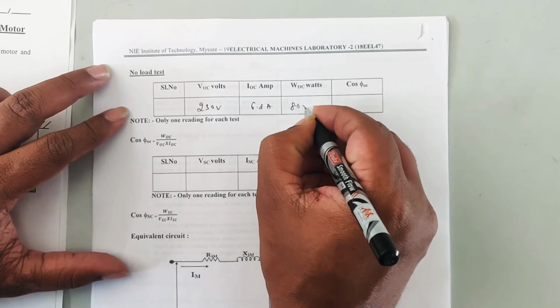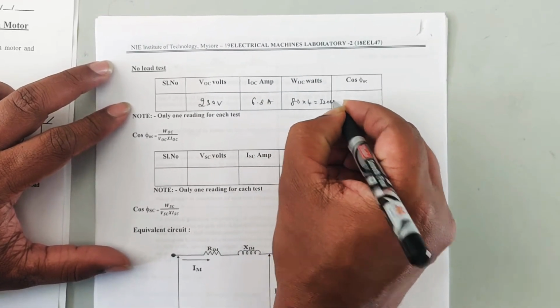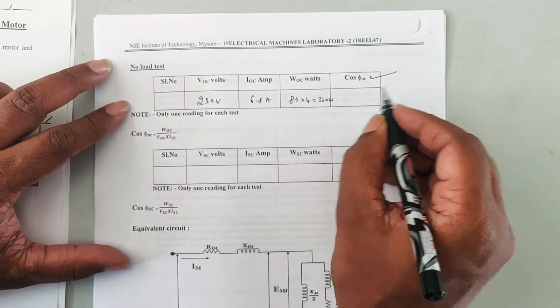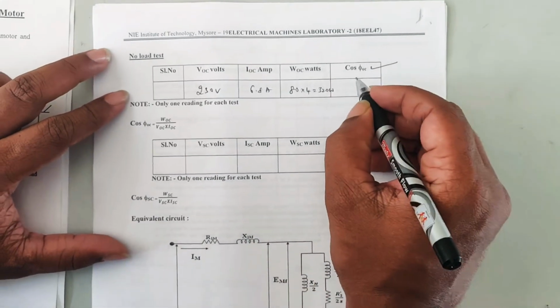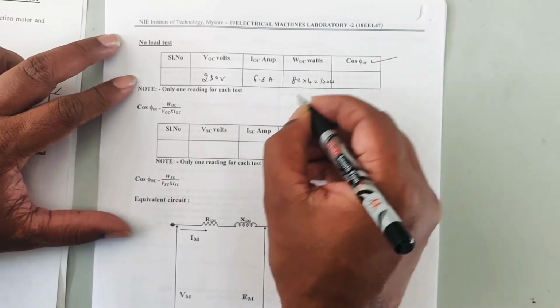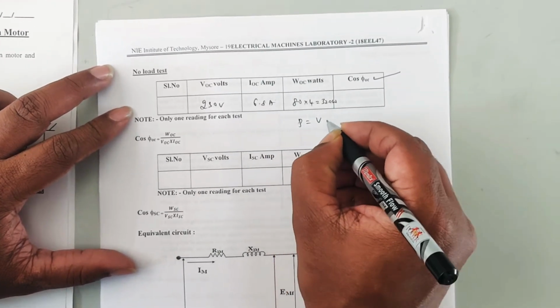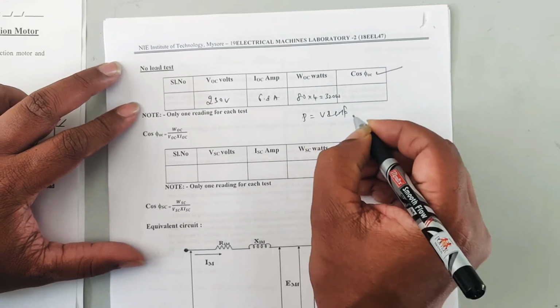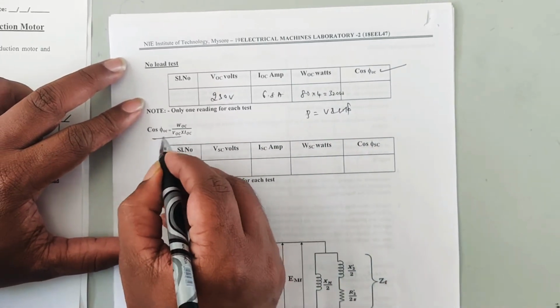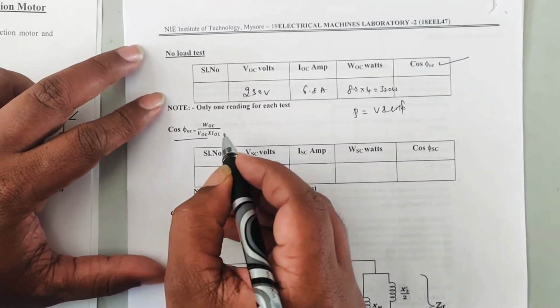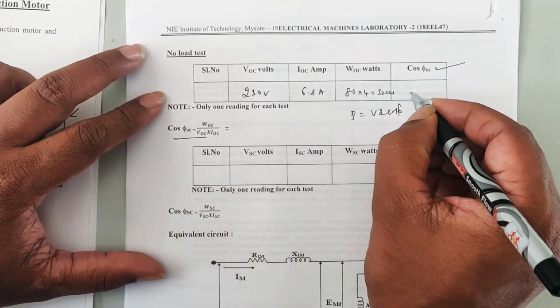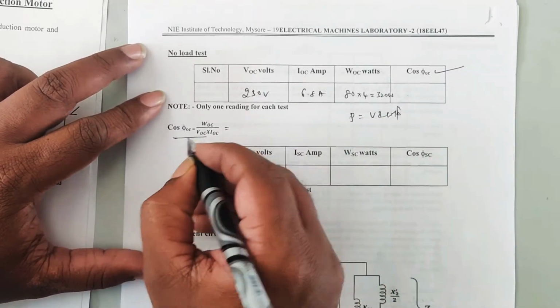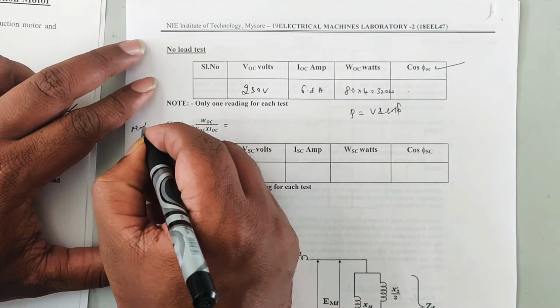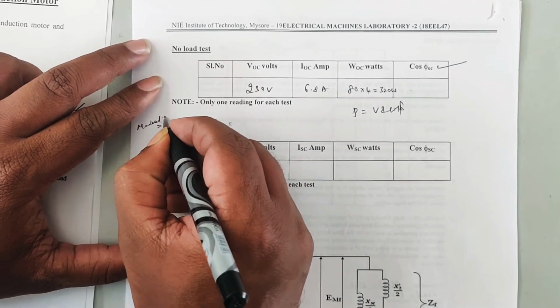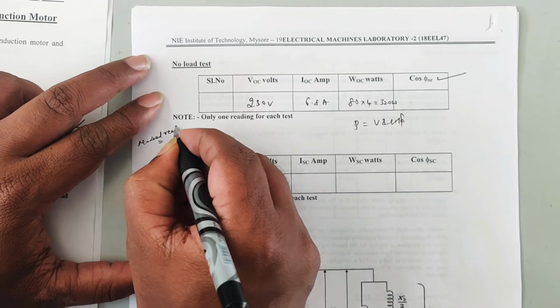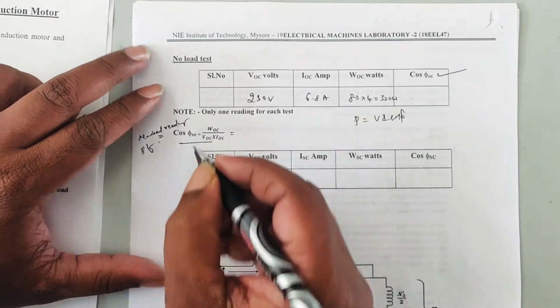What we got is 80 into 4, that is 320 watts. Okay, you have to calculate the open circuit, otherwise no load, power factor. In order to calculate this, you should know the equation P is equal to VI cos phi. If you modify this equation, you get cos phi OC as WOC divided by VOC into IOC. So you can get the cos phi OC value, that is the no load power factor value. Okay, these are all the readings you should take.